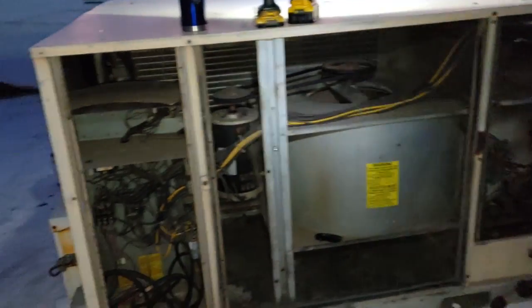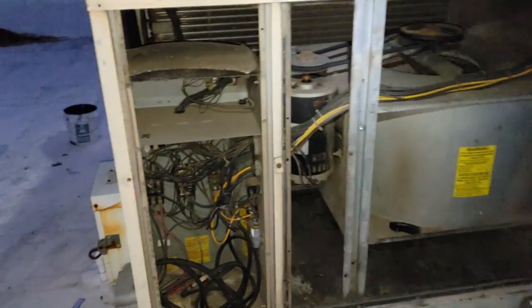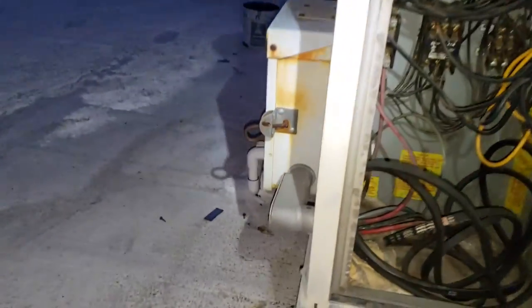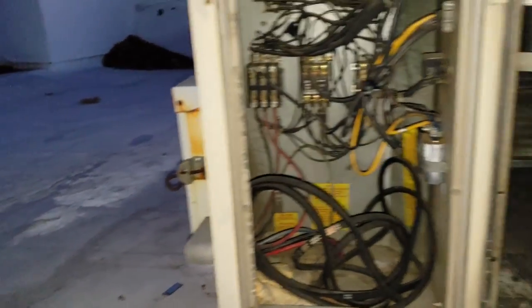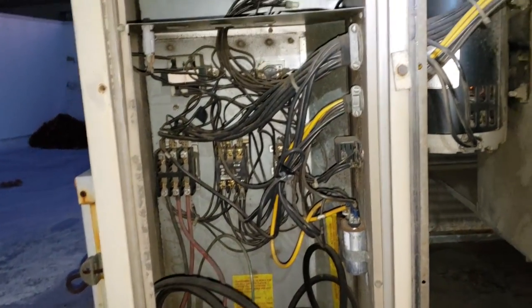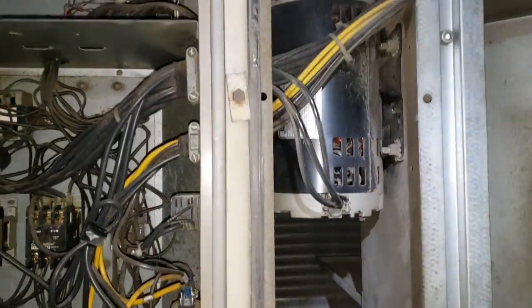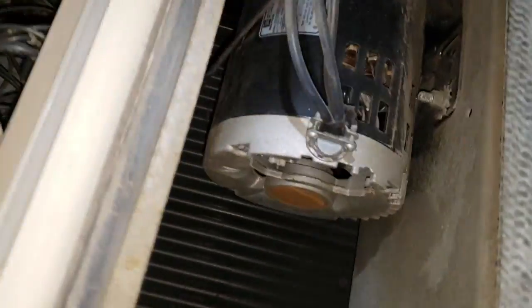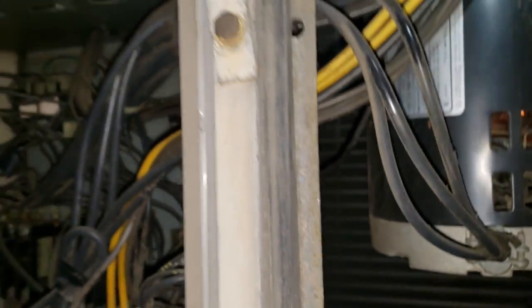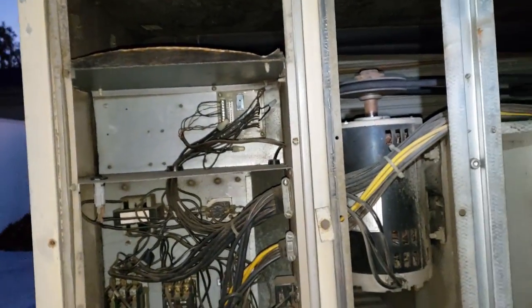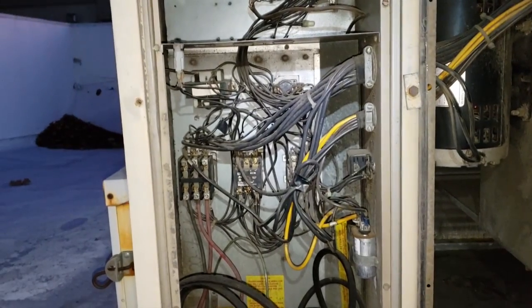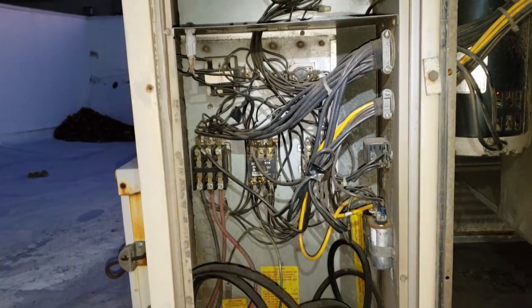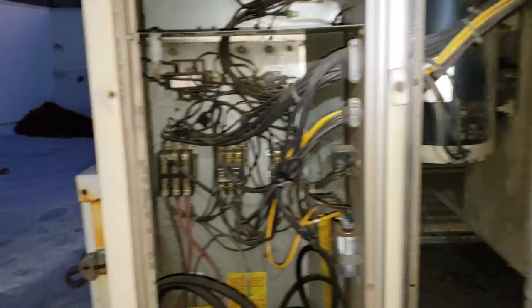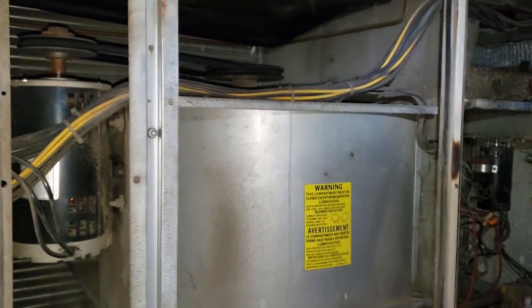So this unit is the one that the smell is the strongest in. We're going to start here. I checked 3-phase power at the disconnect. It has it. The fuses are good. Power's turned off. We're going to go ahead and power up this unit and fire up the indoor blower motor. I pulled the bottom of the indoor blower motor too to inspect the electrical. Don't see anything going on in there, but this has got a really strong burning smell. I have a feeling we've got a motor that's bad. Before I fire it up though, I'm going to check everything to ground just to make sure. And then we'll fire it up and see what happens, and we'll do them one at a time.